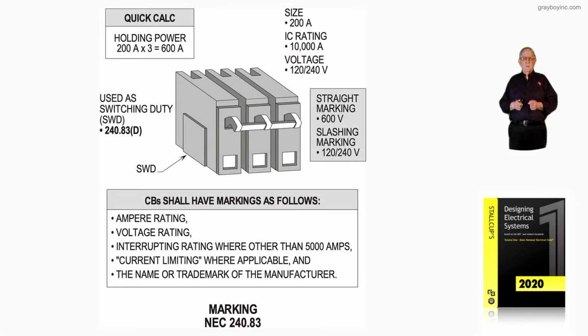Now this illustration deals with marking in accordance with NEC 240.83. This illustration shows the markings on circuit breakers that do not have certain markings. Notice a circuit breaker in the quick calc will basically hold 3 times its rating at 600 volts or less. So a 200 amp circuit breaker will hold about 600 amps when you do your 3 times 200. Remember the fuse now at 200 amps times 5 would hold 1,000 amps.